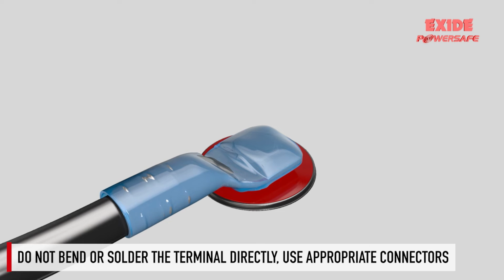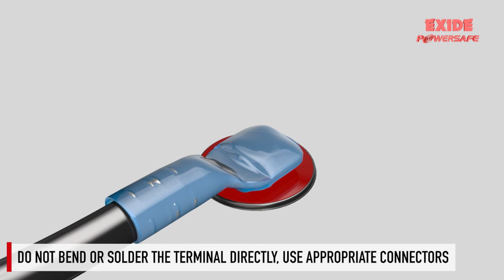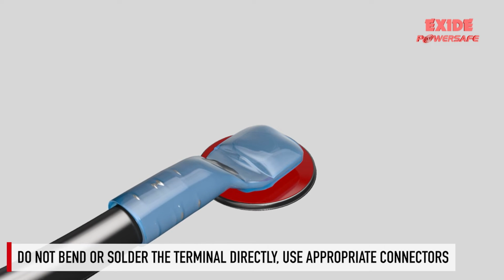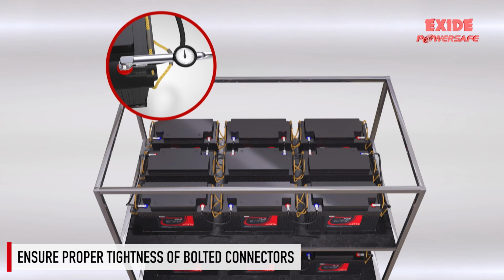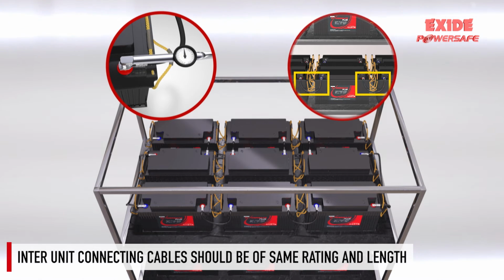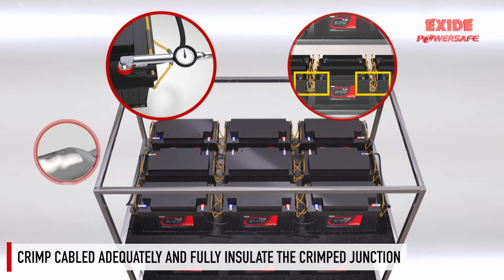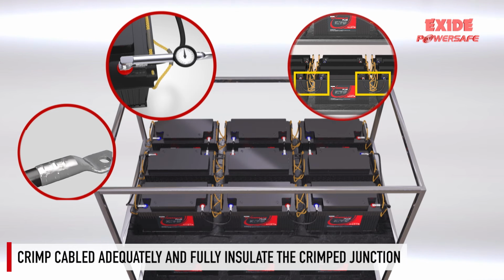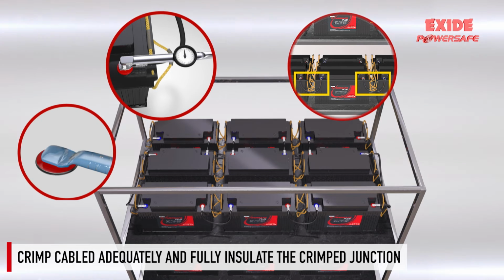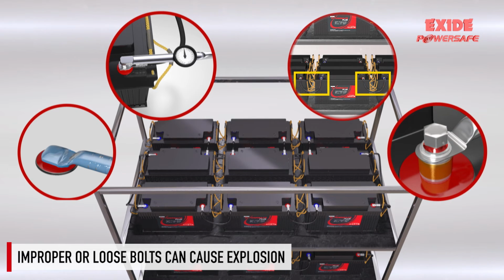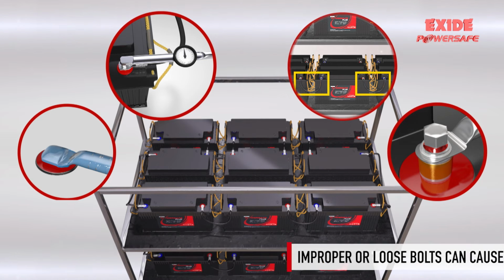Terminals are not to be bent or soldered directly. Appropriate connectors should always be used. Proper tightness of bolted connectors should be ensured. All inter-unit connecting cables must be of same rating or cross-section and of the same length. Cables are to be crimped adequately, and the crimp junction is to be fully insulated. Improper or loosely tightened bolts can create a spark leading to an explosion.